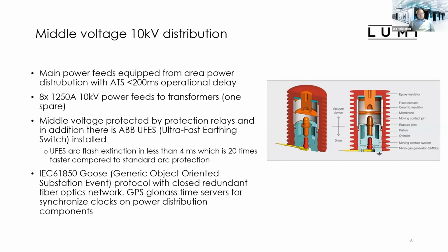And we also have this IEC 61850 standard Generic Object Oriented Substation Event protocol in place, which is on closed redundant fiber optics networks. And there are GPS and GLONASS time servers for synchronous clocks on power distribution. This protocol is a communication model defined by the IEC standard, which uses a fast and reliable mechanism to group any format of data in the dataset and transmit it across the communication network within 4 milliseconds.